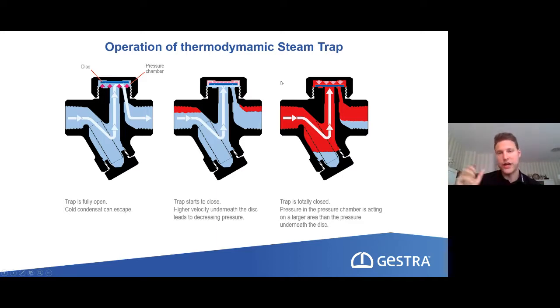If we have air in our system, this was the second basic requirement, air travels through the system rather as fast as steam, not as slowly as condensate. So it's also at, I would say, 20 to 25 meters per second. And what does that tell this steam trap? As soon as we have air, the air will also flow as fast as steam, and it will tell the steam trap to close. And this is what it's doing.